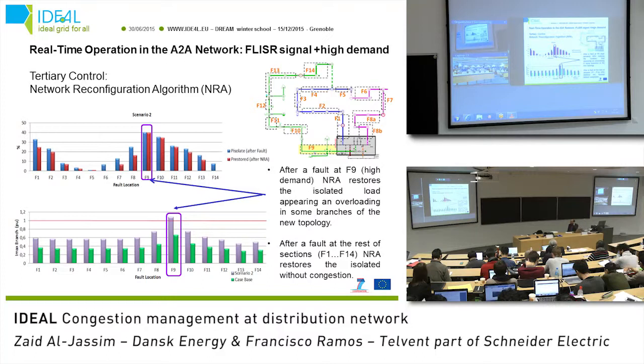We have done some simulations to see the performance of the network reconfiguration algorithm. These simulations were on the A2A network. We have simulated several faults. You can see the figure here on top, where we have blue and red bars. The blue bar indicates, after a fault situation, how much power has been lost, or how much share of the load has been lost. And the red bar shows the solution that has been proposed, or the action of the tertiary controller, or the action of the network reconfiguration algorithm: how much power has been restored, or how much load has been reconnected to the network.